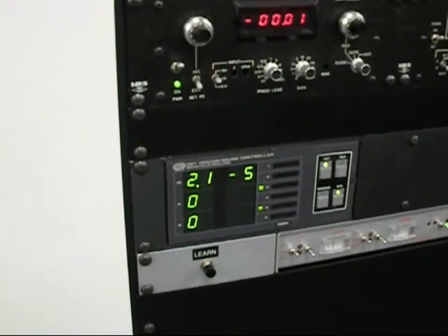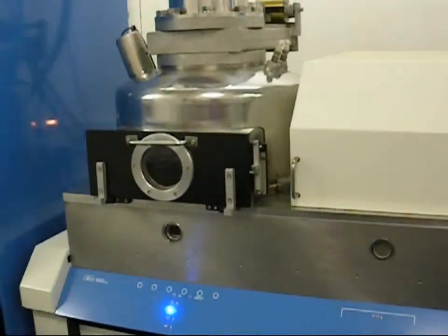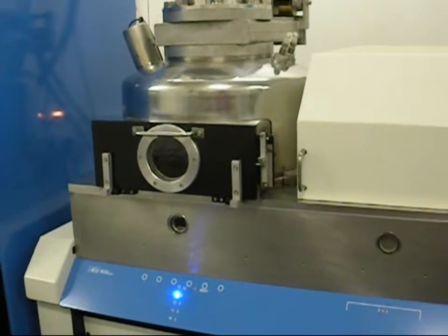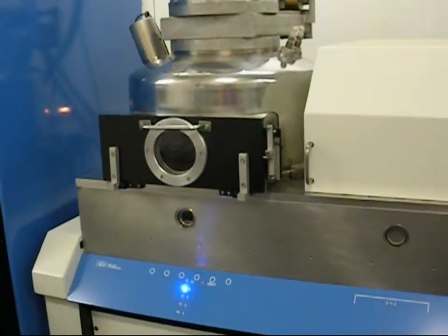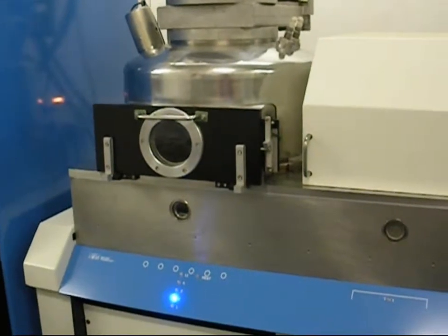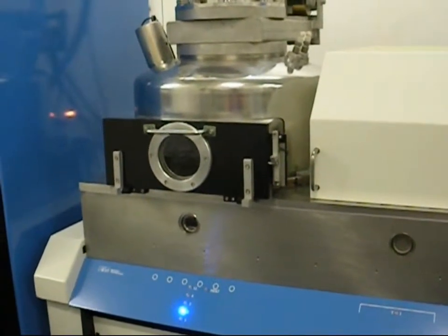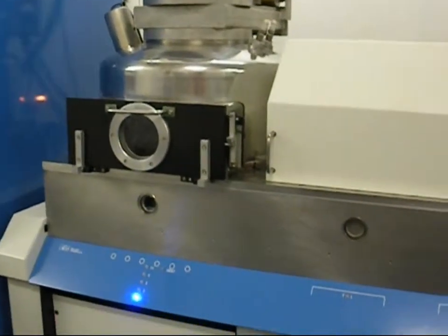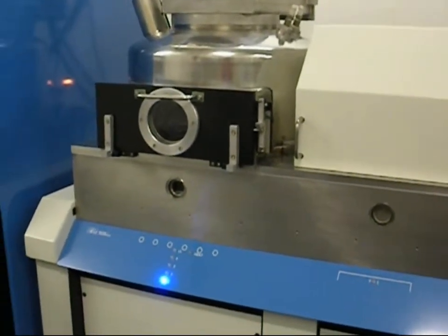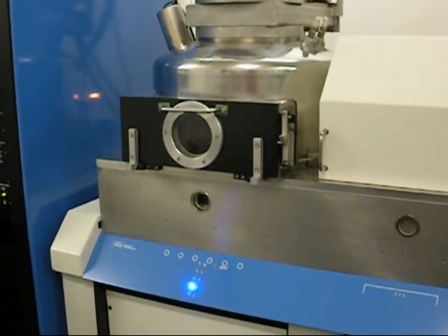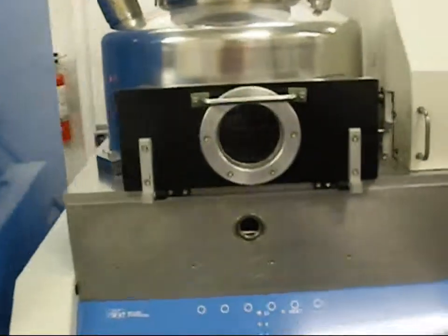The pallet exchange sequence is accomplished by a series of vertical up and down positioning steps by the 5-level load lock seal plate. Upon completion of the exchange process, the pallet will be loaded into the main process chamber onto the pallet carrier. A finished process substrate pallet will be placed on the lower level of the load lock elevator. At this time, the load lock elevator will be raised to its highest position level and its seal plate will isolate the two chambers.